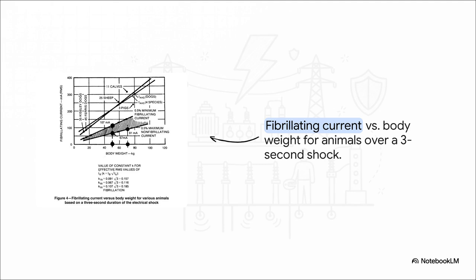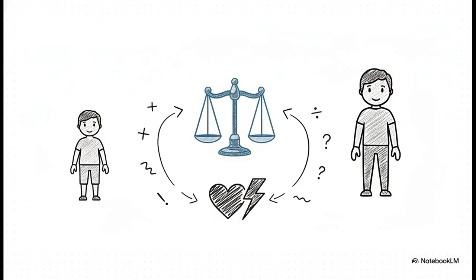They conducted extensive testing on animals of various weights, like calves, sheep, pigs, and dogs, as you can see mapped out here. This foundational data allowed the IEEE to establish highly rigorous, mathematically sound safety thresholds for human beings, based entirely on body weight. Taking that data, engineers literally used 2 standardized human body weights to calculate the safety limits of the entire power grid. They designed for a 50-kilogram person, which represents a smaller adult or worker, using a mathematical constant of 0.116, and they calculate for a 70-kilogram person, using a constant of 0.157. These constants are absolutely essential because they help engineers calculate the absolute maximum safe fault duration a person can withstand before going into cardiac arrest.